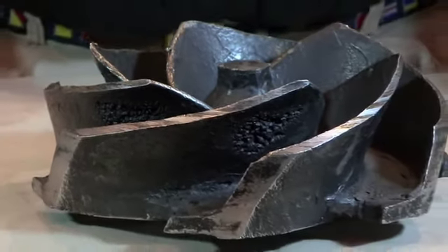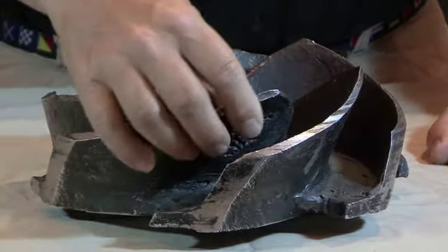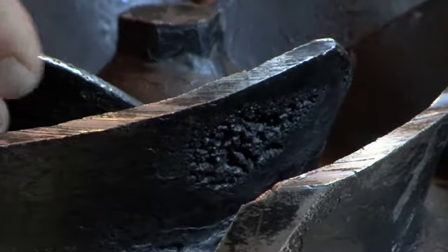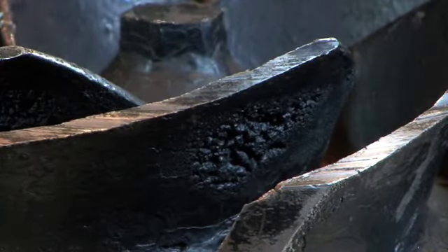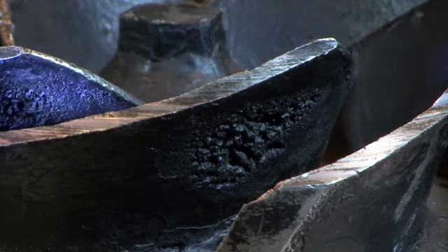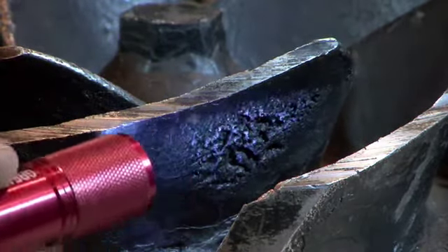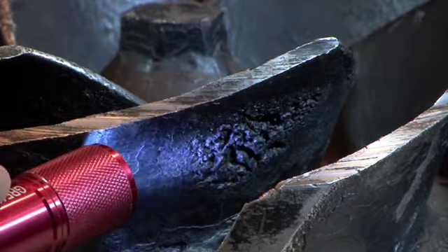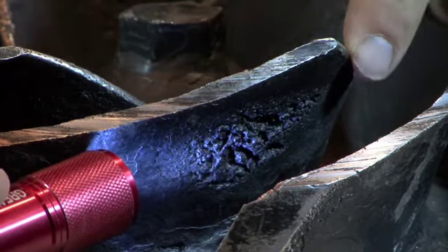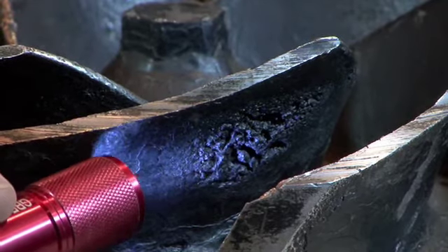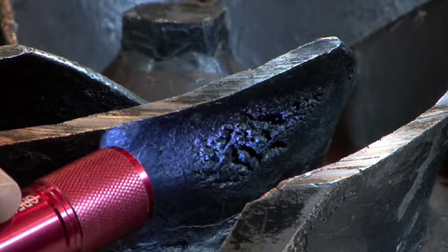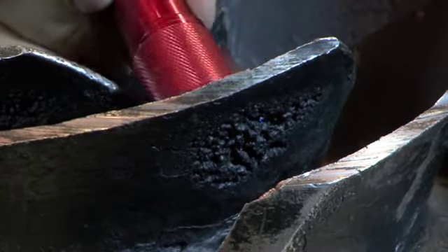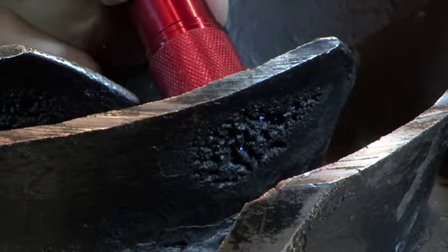But one of the main features I want to point out for this one is this damage right about here. This damage is typical of suction recirculation. You can see the eroded effect, the pitted effect. If I take a flashlight and shine it across at an angle, you can see how that looks under the light. Very, very deep pits. This is on the back side of the impeller blade. It's on the leading half of the impeller blade. So this was undoubtedly due to suction recirculation. In fact, the damage is so bad that if I shine the light on the back, you can actually see on the camera light shining through. It had eroded all the way through.